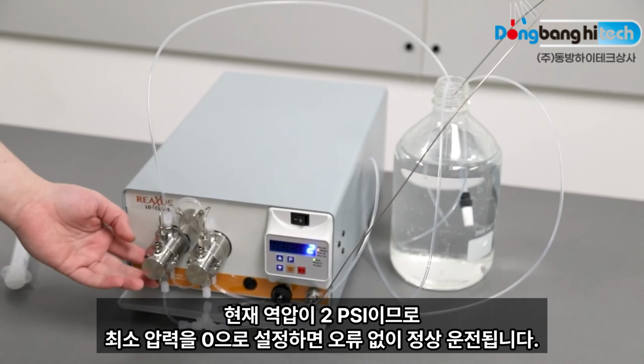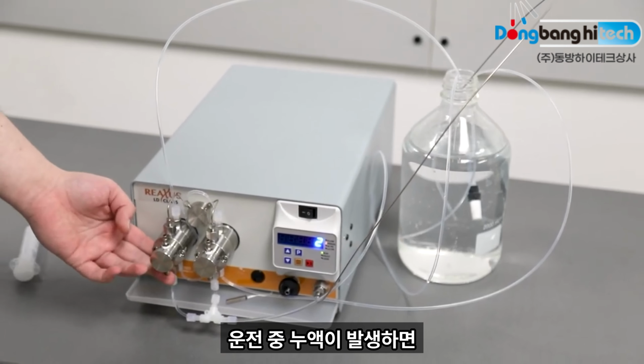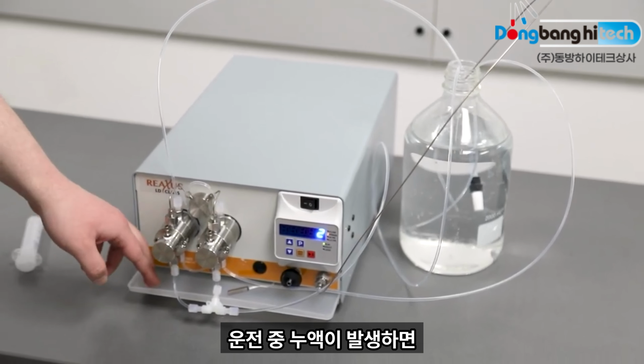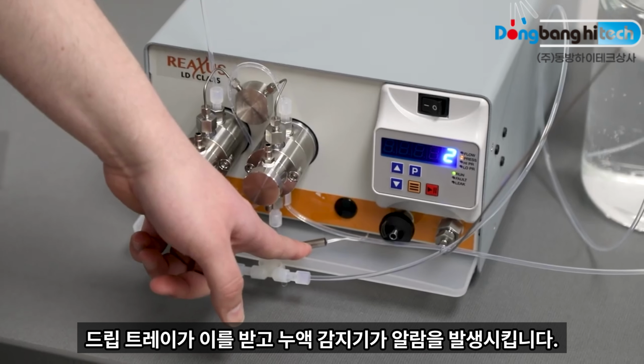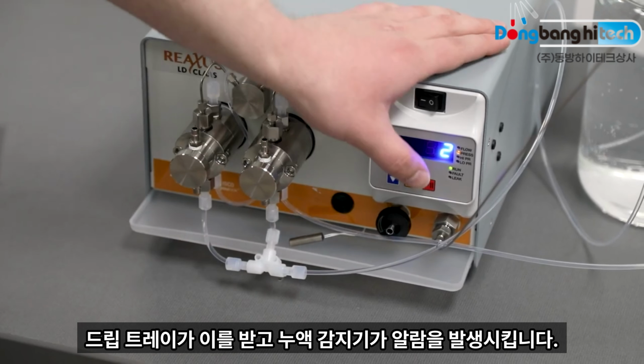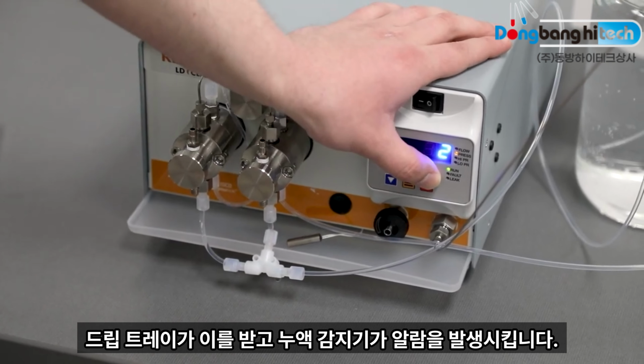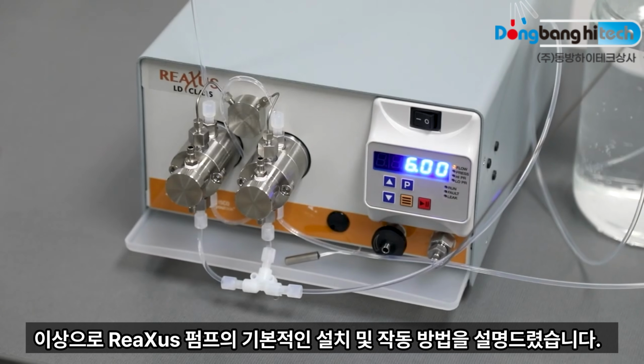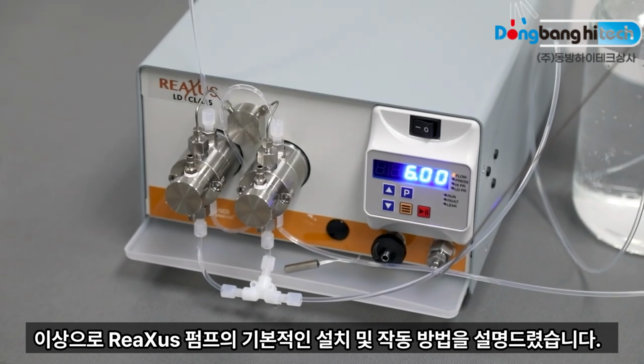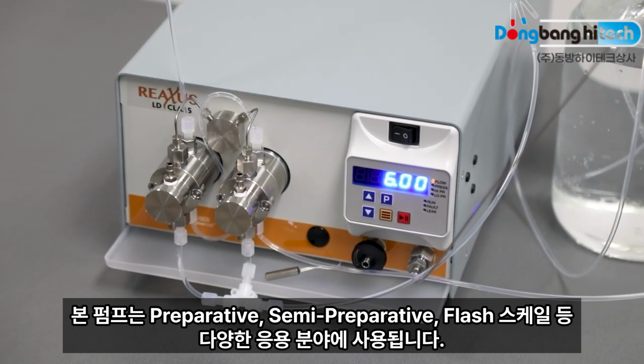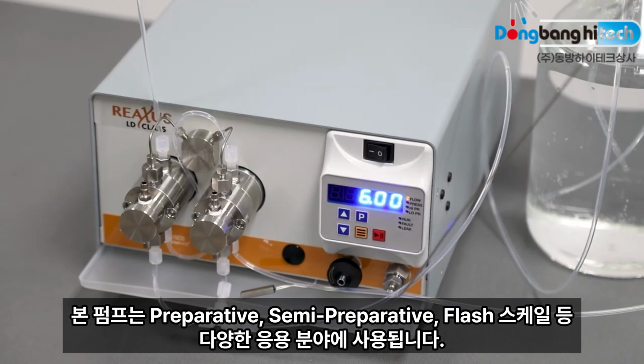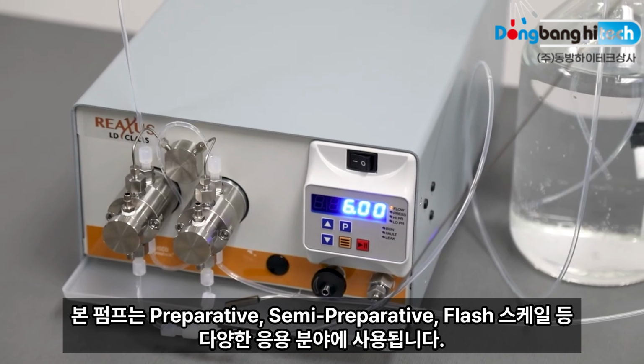If any leaking occurs at the pump heads during operation, it will be caught by the drip tray, and our leak detector will recognize that solvent in the drip tray and throw our leak alarm. Those are the essential steps for operating the ReaXus pump. They can be used in a wide variety of applications: preparative, semi-preparative, flash scale.